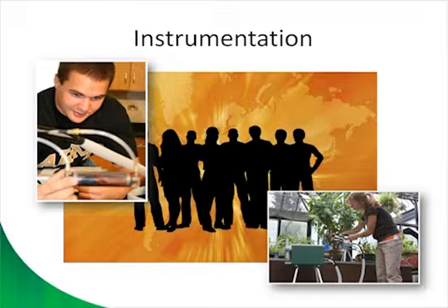Thanks, Kristen. I'm going to go ahead and switch our screen so we can see the front panel of our LI-6400 portable photosynthesis system. And what you have before you is actually a real-time graph. I have the chamber clamped onto a maize plant in the greenhouse, and I'm communicating via Ethernet. So right here in our room, I'm able to control and operate the instrument and also view it from here.